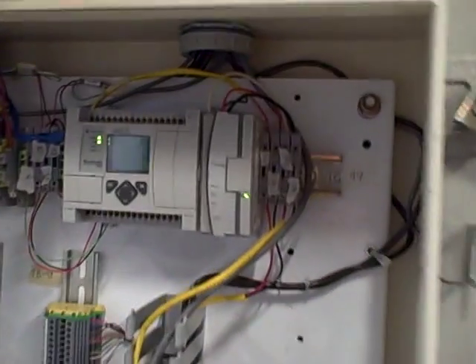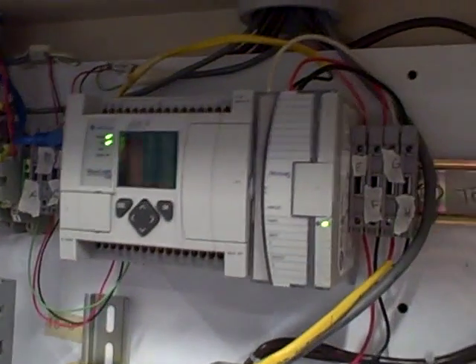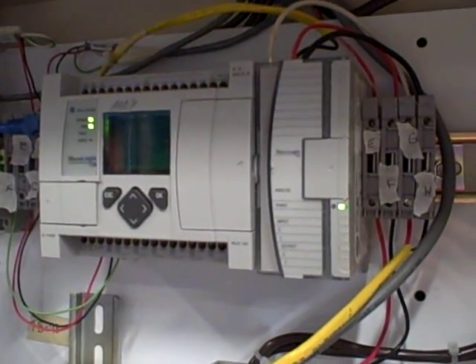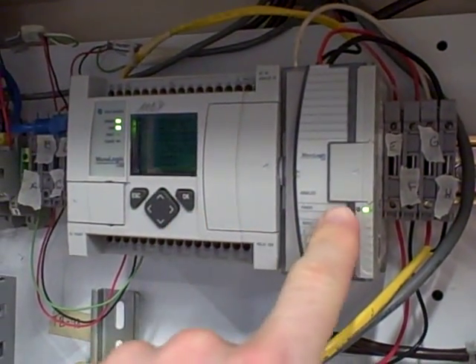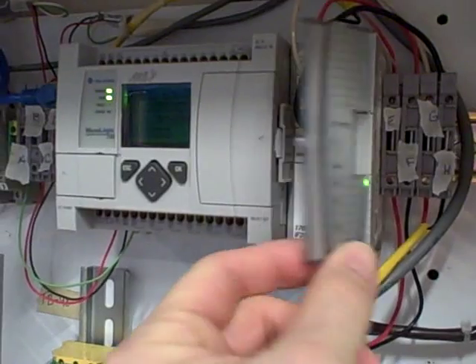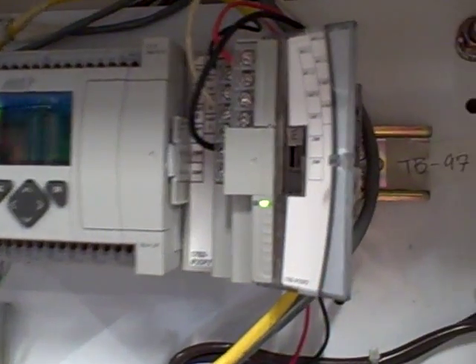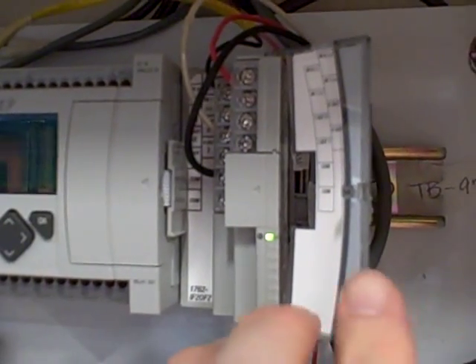What I'd like to demonstrate to you right now is the actual control system itself, which consists of an Allen-Bradley MicroLogix 1100 controller right here, with an add-on unit, an IF2, OF2 model analog I/O card. This particular card has two channels of analog input and two channels of analog output, 4 to 20 milliamps both.